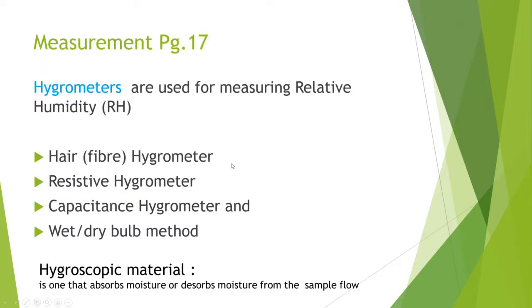There are several types of hygrometers: the hair hygrometer, which is very primitive; resistive and capacitive, which are both electrical property-based; and the wet-dry bulb method. The first three rely on hygroscopic materials — materials with an affinity for moisture that absorb or desorb moisture from the sample flow. The wet-dry bulb method is quite different.